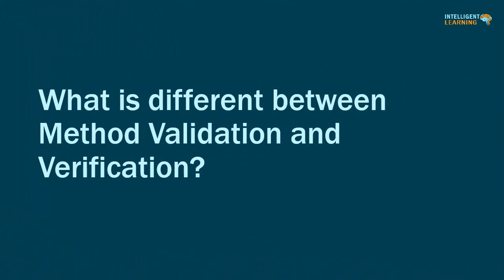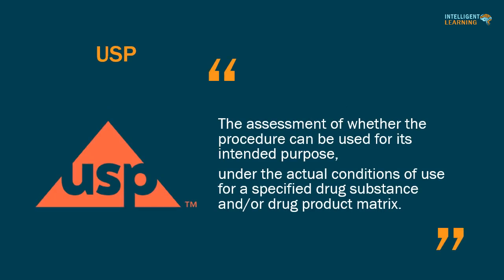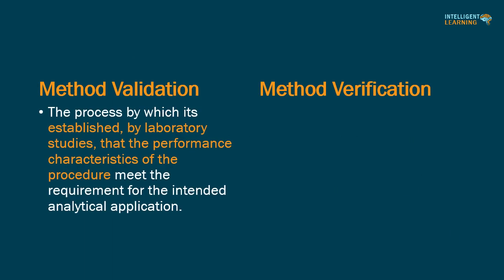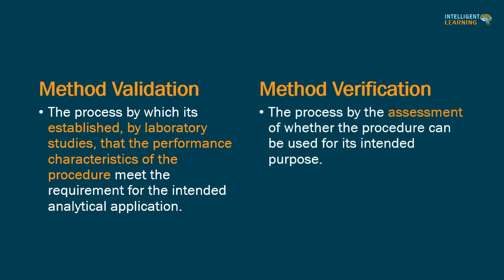What is the difference between method validation and verification? As per USP, verification is the process of assessment of whether the procedure can be used for its intended purpose under the actual conditions of use for a specified drug substance and/or drug product matrix. Method validation is the process by which it is established by laboratory studies that the performance characteristics of the procedure meet the requirements for the intended analytical application. In short, method validation is establishment, while method verification is assessment of whether an analytical method can be used for its intended purpose.